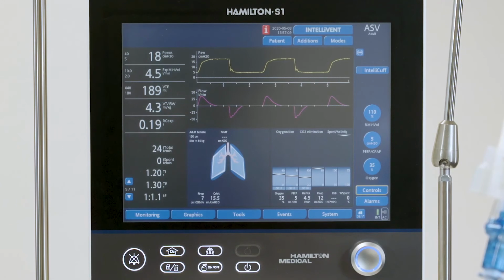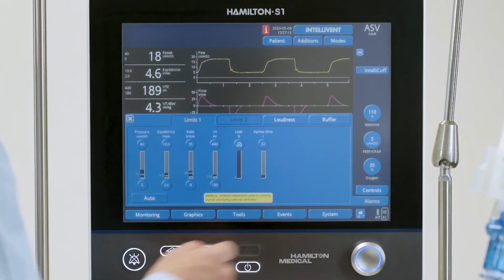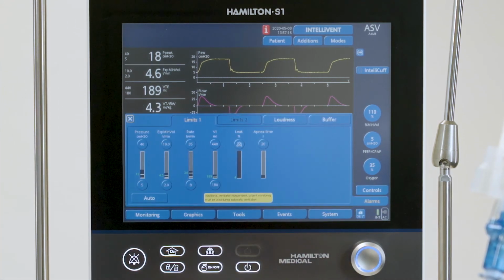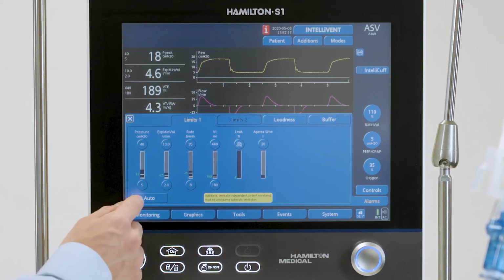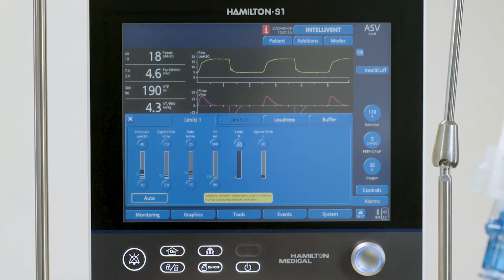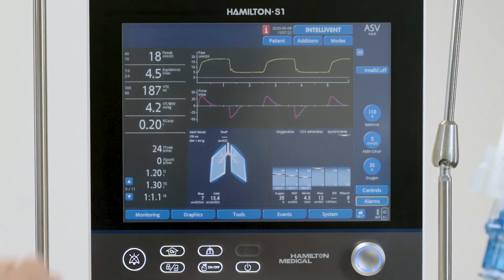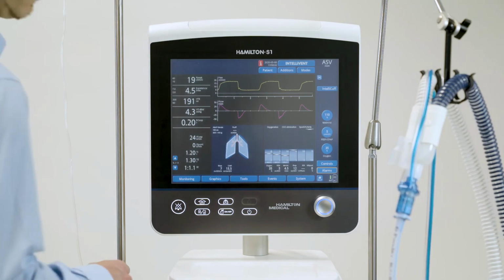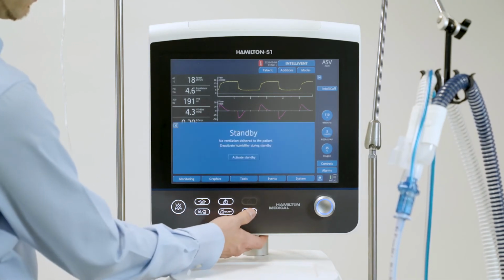After changing the ventilation mode, you should review the alarm settings. To review and adjust the alarms, touch the Alarms button. Then, select the Alarm control and adjust it. To set alarm limits quickly, touch the Auto button. All alarm limits, except for the tidal volume and apnea alarms, will be set automatically around the current monitoring parameter values. To stop ventilation, press the Standby key.